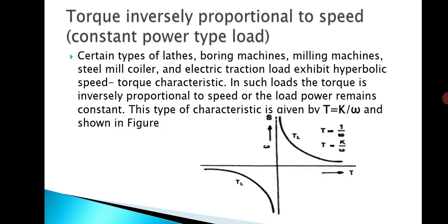Next, torque inversely proportional to speed — this is the constant power type load. Certain types of lathes, boring machines, milling machines, steel mill coilers, and electric traction loads exhibit hyperbolic speed-torque characteristics. In such loads, the torque is inversely proportional to the speed and the load power remains constant. When speed increases, torque decreases, and when torque increases, speed decreases.